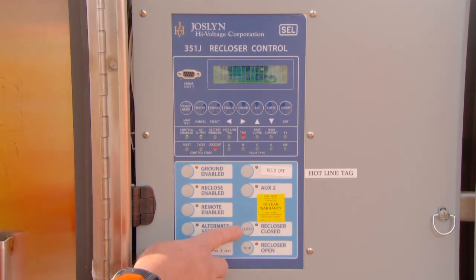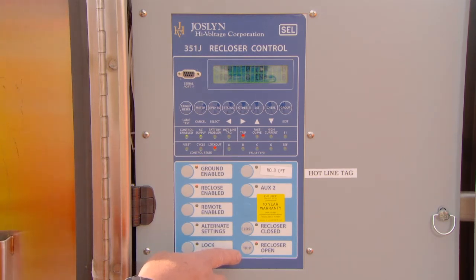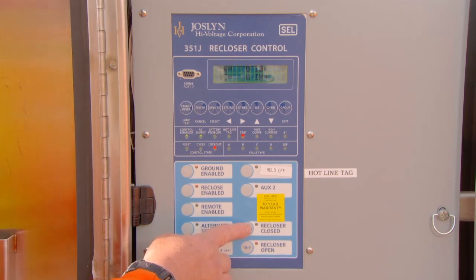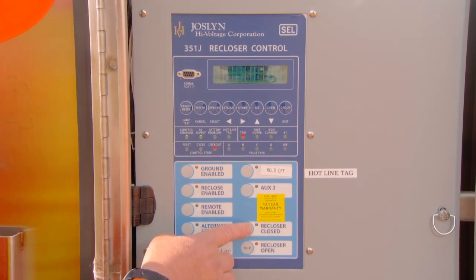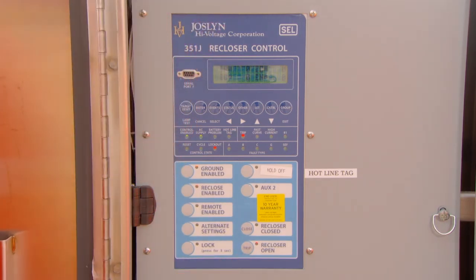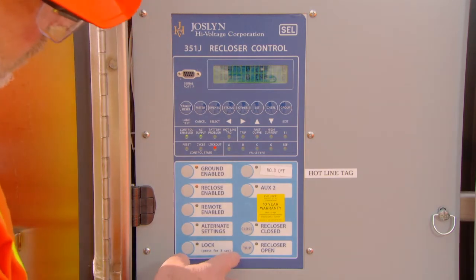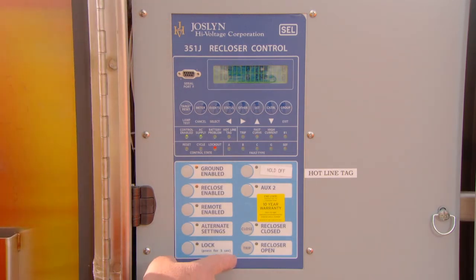Lastly, we have the trip and close buttons. The closing process utilizes a mechanical spring-driven closing mechanism. After pushing the close button, you will see the LED light begin to flash green. You will then hear the sound of the motor beginning to charge the trip springs and close the contacts. The close button indicator will now turn green.